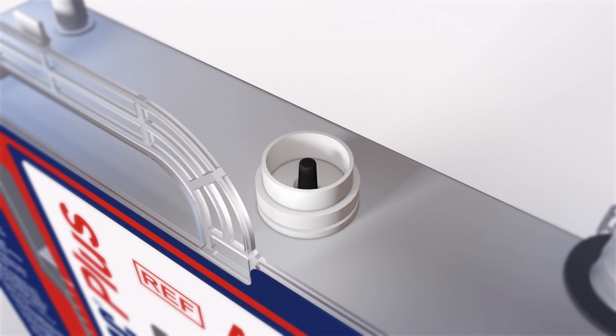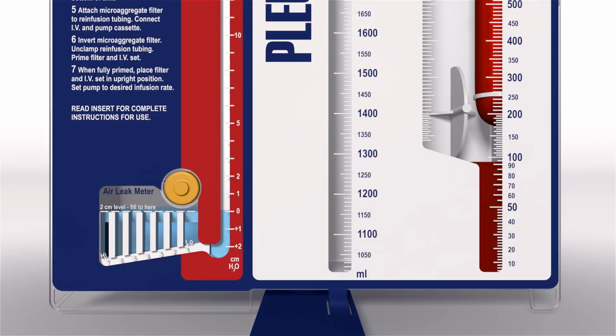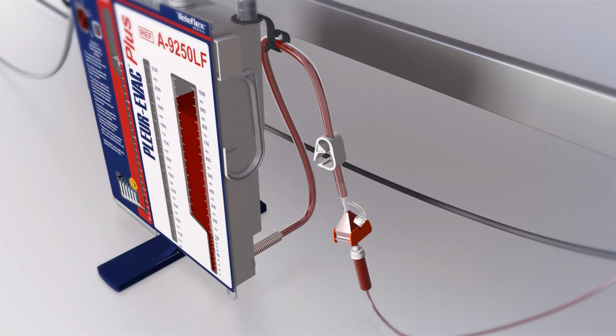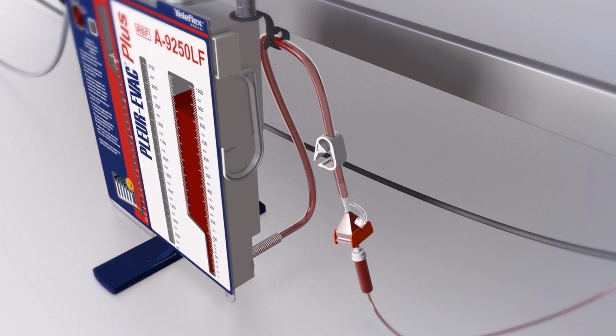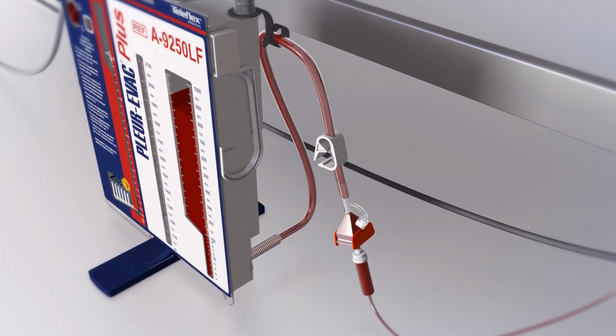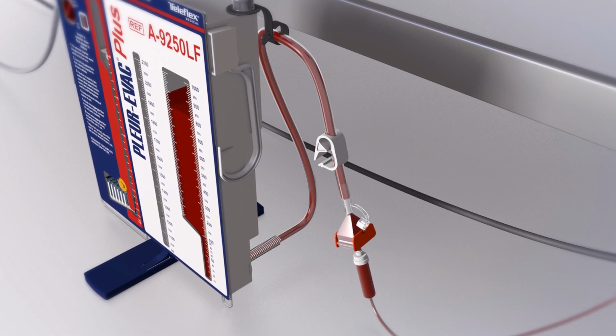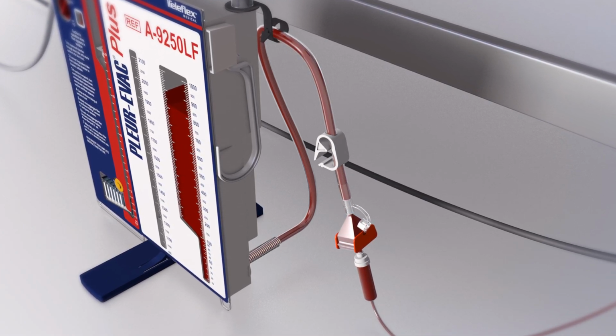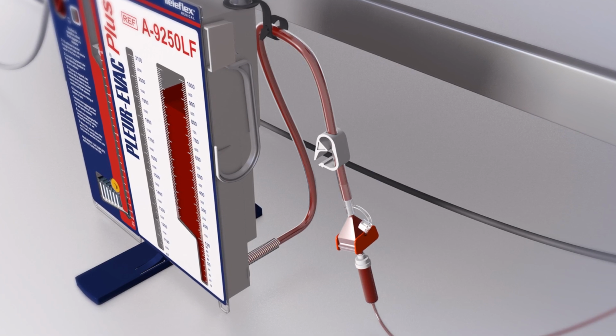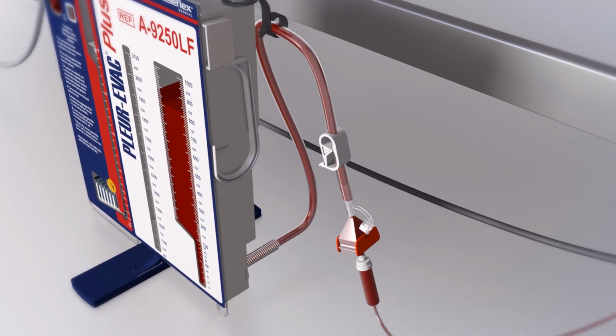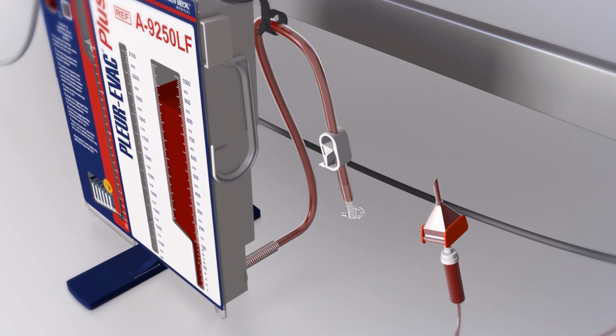If necessary, as previously mentioned, the manual filtered high-negativity relief valve may need to be depressed to offset excessive negativity buildup caused by the IV pump. Note that during continuous flow autotransfusion, the fluid in the collection chamber must never fall below 50 milliliters. Eventually, you may decide to discontinue reinfusion therapy and use the device as a simple chest drainage collection unit. When disconnecting from the infusion pump to discontinue continuous reinfusion, be sure the clamp on the reinfusion tubing is in the closed position and the tethered cap of the exit port is in place.